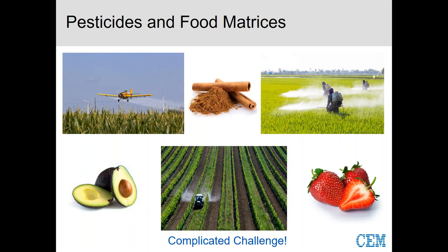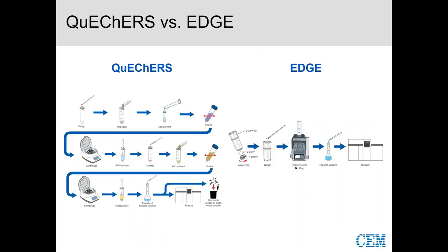When we've got such a complicated challenge, if we have one instrument and one method protocol that can apply, then that's going to be very favorable. Traditionally, the extraction of pesticides from food matrices is done with the QuEChERS method. What I want you to get from this visual is the number of steps involved for QuEChERS versus EDGE. What we're bringing to the table with the EDGE is automation — we're able to eliminate all the multiple manual steps currently required for the QuEChERS method. EDGE is an alternative for the extraction of pesticides from food matrices. It's not doing the exact same chemistry; it's pressurized fluid extraction, a different technology, but it brings automation and other benefits to the table.